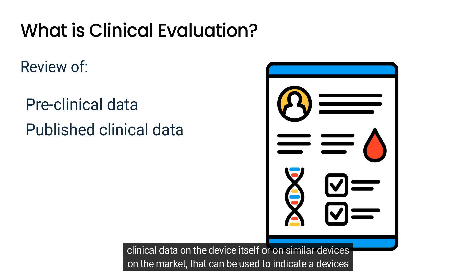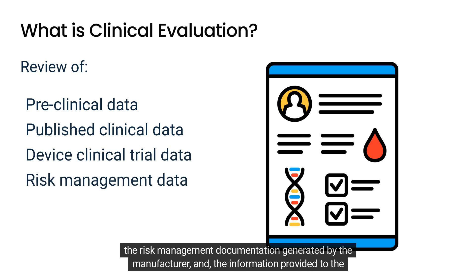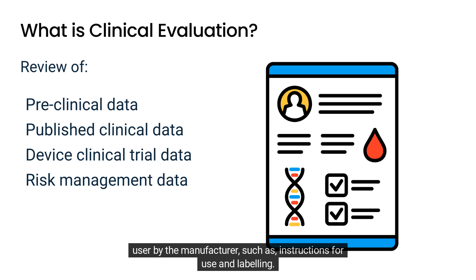Clinical evaluation also encompasses a review of any clinical data pertinent to the medical device, in the form of published clinical data on the device itself or on similar devices on the market that can be used to indicate a device's performance and safety. It also reviews any non-published clinical studies or data generated by the manufacturer. It assesses the risk management documentation and the information provided to the user, such as instructions for use and labeling.